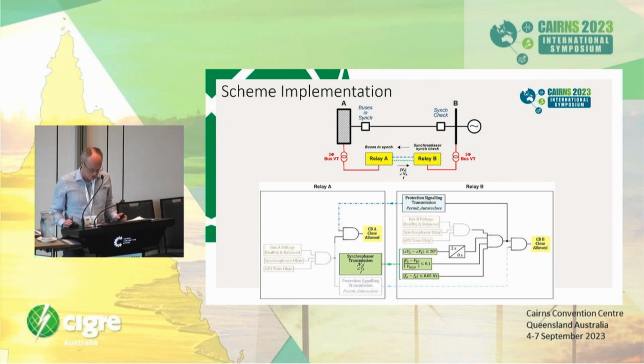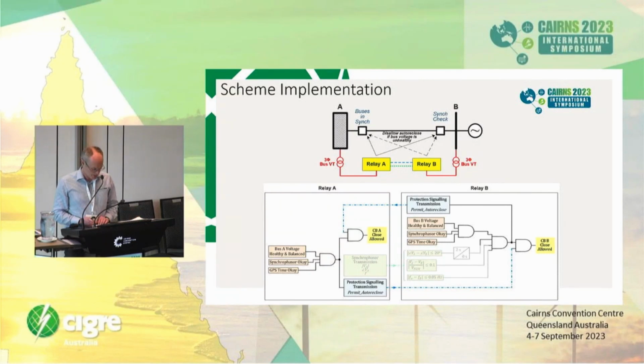Synchrophasor protocol is used to continuously transmit bus A red phase voltage, phase and frequency information to relay B. Relay B is continuously using the received data together with bus B voltage information to determine whether an asynchronous condition exists. If bus A is in synchronism with bus B, then relay B will send a permit auto-reclose signal to relay A. Circuit breaker A close is then allowed. This is used instead of a dead line charge. If bus A voltage is healthy and balanced, relay A will send a permit auto-reclose signal to relay B, and provided bus B voltage is healthy and balanced, circuit breaker B is allowed to close.